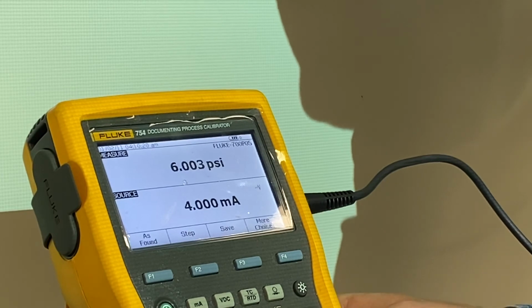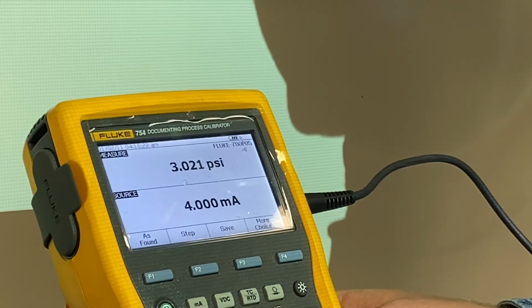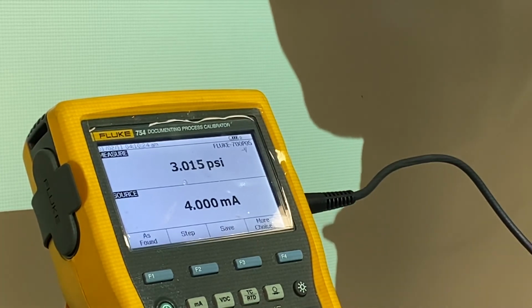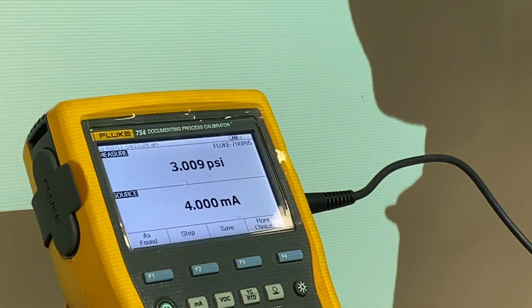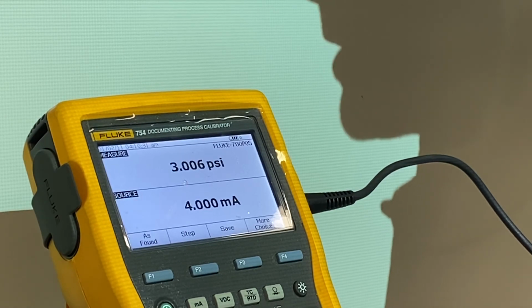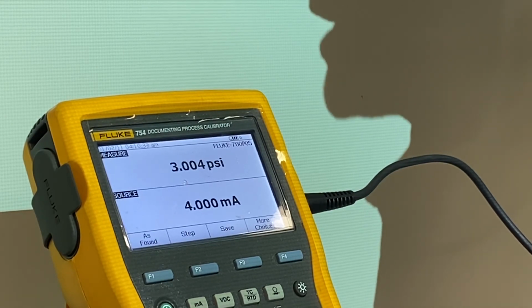Okay, and then again at our zero, at 4 milliamps, we should be at 3 psi. Okay, and that's all the steps it takes to calibrate an I to P transducer.